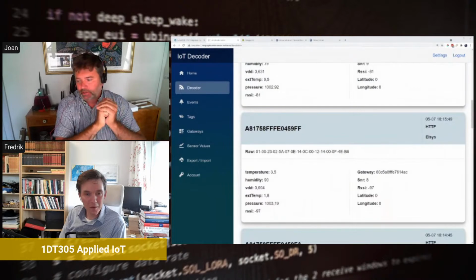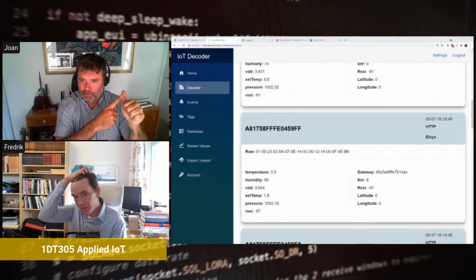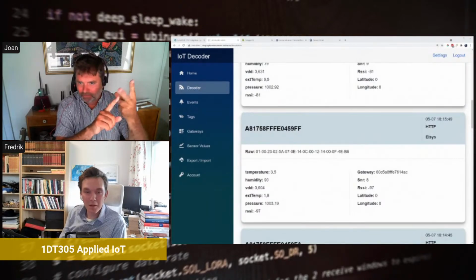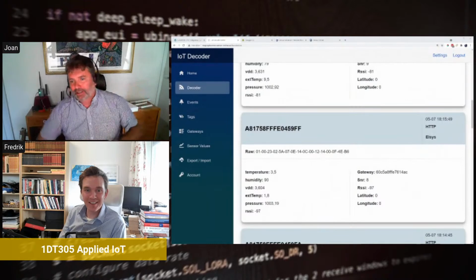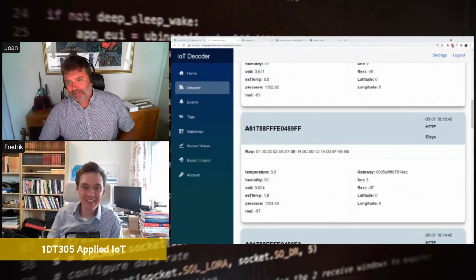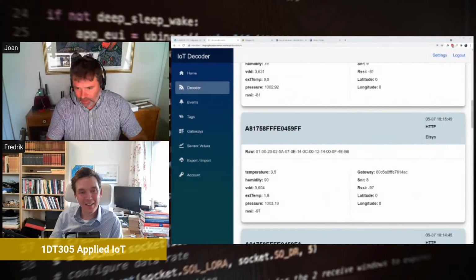I usually ask, how many sensors can you install with an electrician? A gateway costs around 10,000. I have a rule of thumb: 10,000 Swedish krona, 10,000 meters range, and it can serve many thousands of sensors. Just normally, with working labor cost and expenses, 1 or 2 days with an electrician equals the cost of one gateway. So after that you're on the plus side if you use wireless sensors.